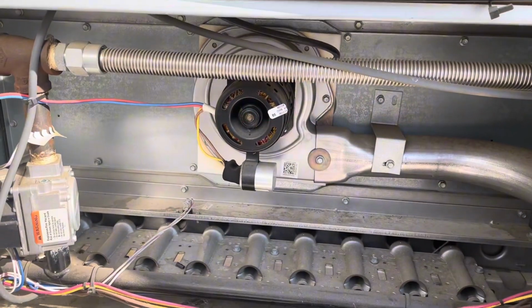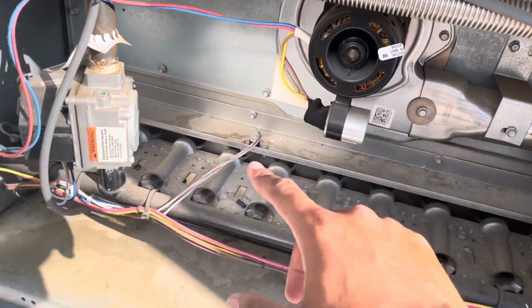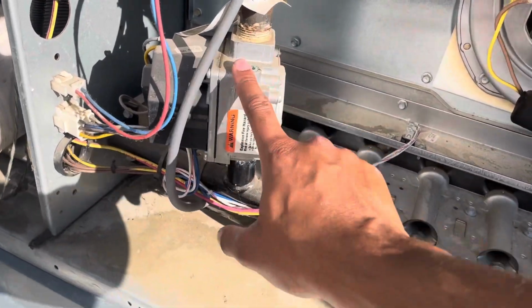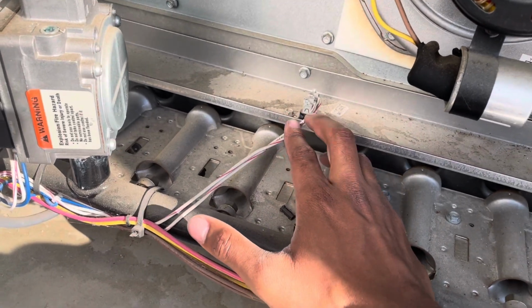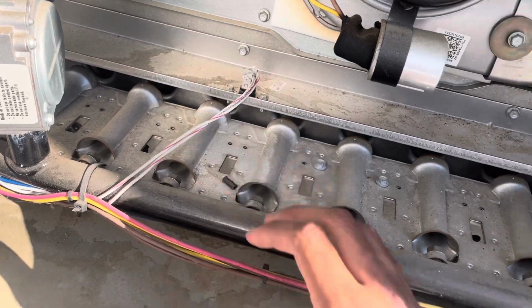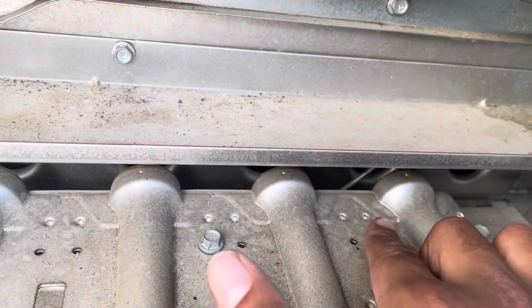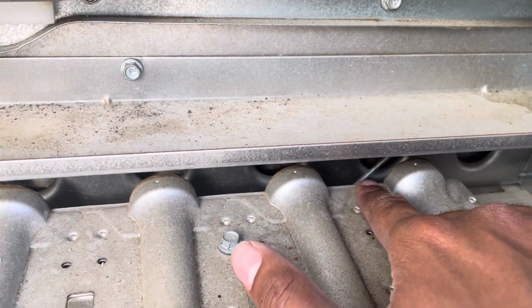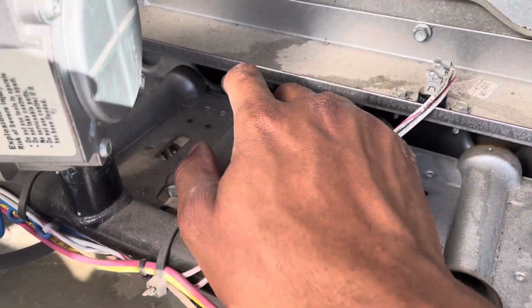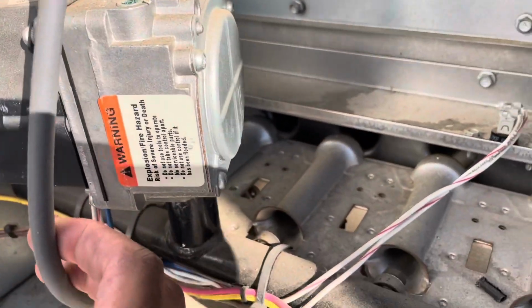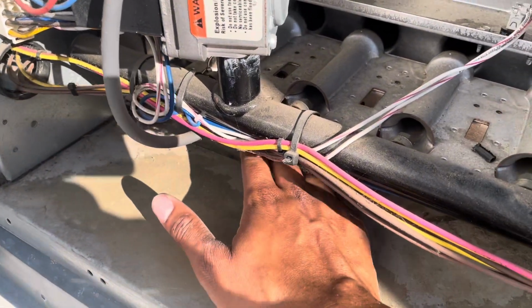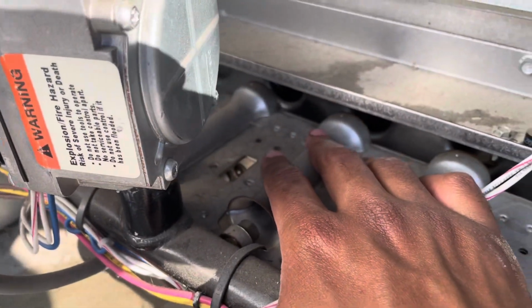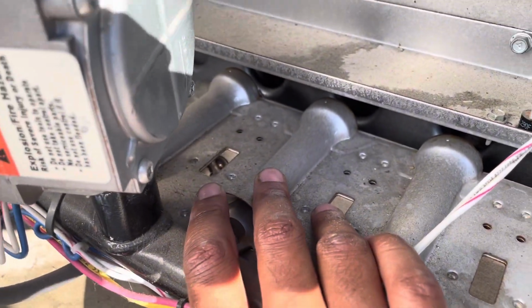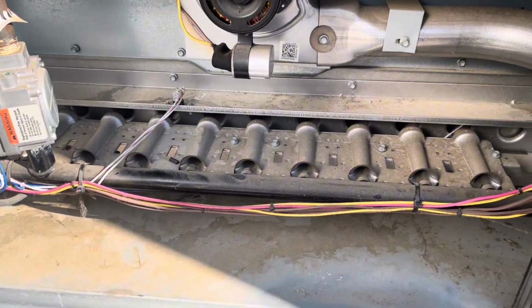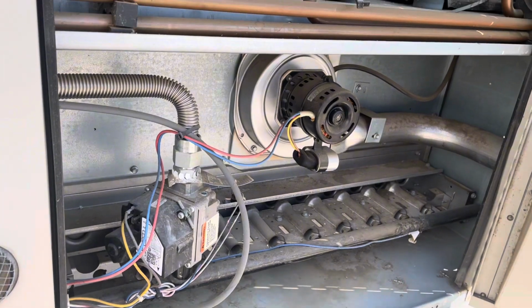All right. So there's your inducer motor with your capacitor here. There's the gas valve. I believe this is a 2-stage gas valve. This is your flame rollout switch. And over here, you can see that rod right there. That is the flame sensor. And right here, I don't know if you can see that, but this thick wire goes into the burner section. That's your spark or your igniter. That's what ignites the gas as it's flowing through the manifold. And it's exactly the same on the other side.